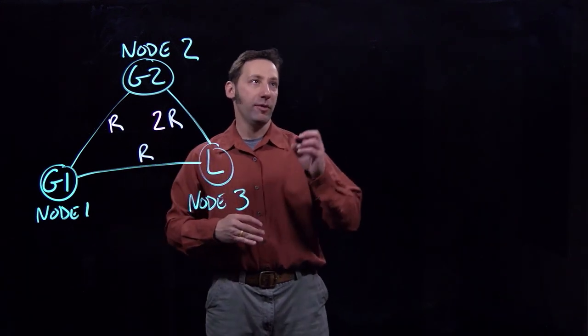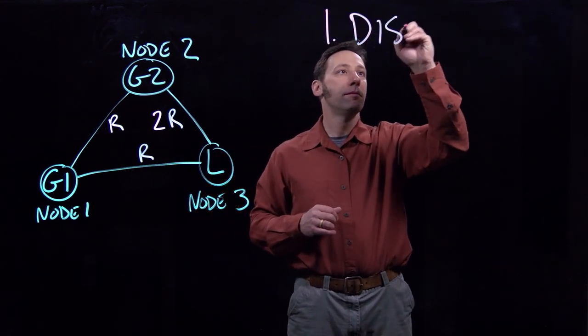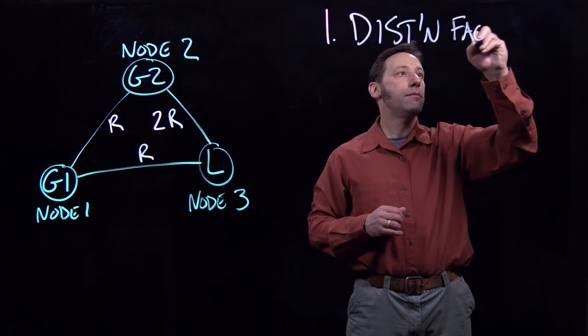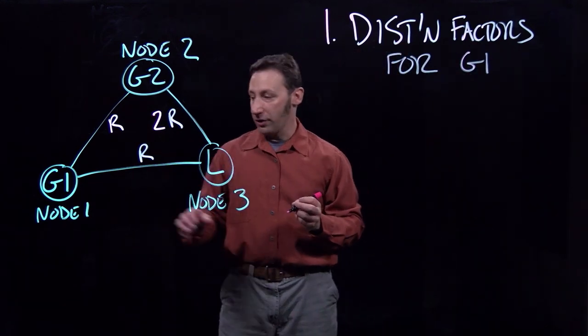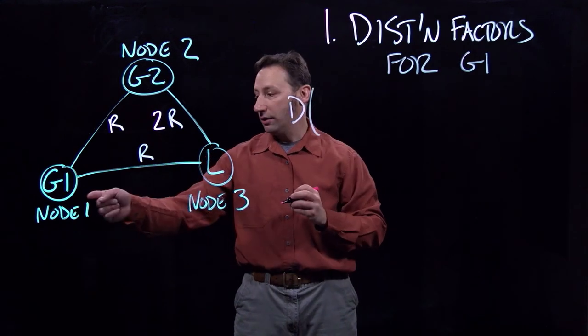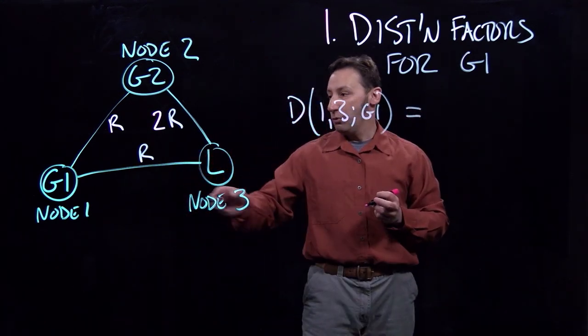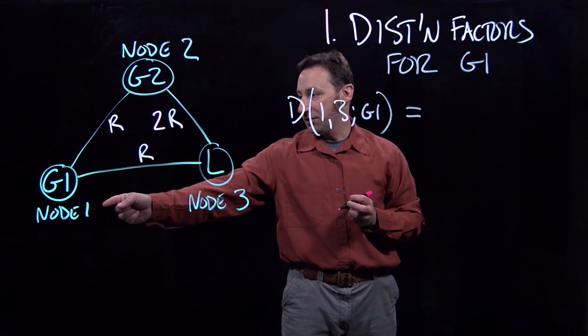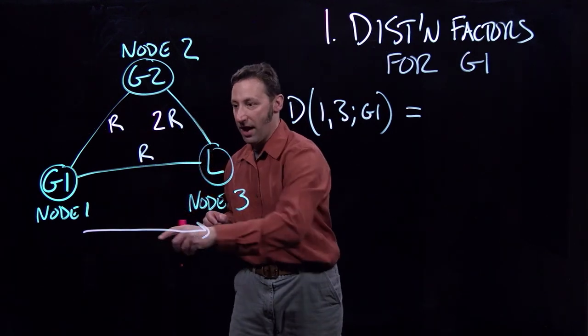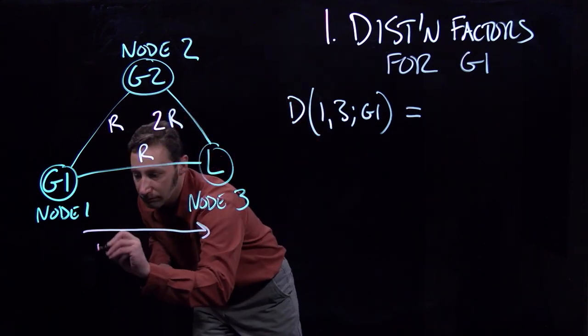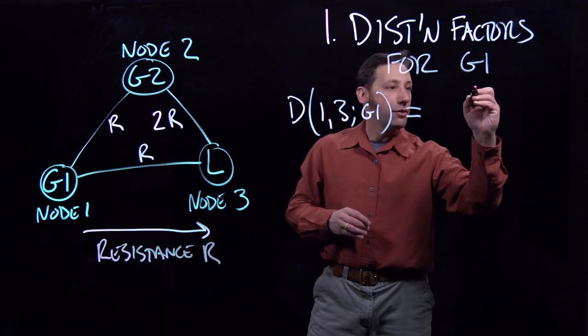The first step is to calculate the distribution factors for G1. We're going to start with the distribution factor on line 1 to 3 from G1. The numerator is going to be the inverse of the resistance of the path that goes from node 1 to node 3 — one path with resistance R. So that's going to go in the numerator.